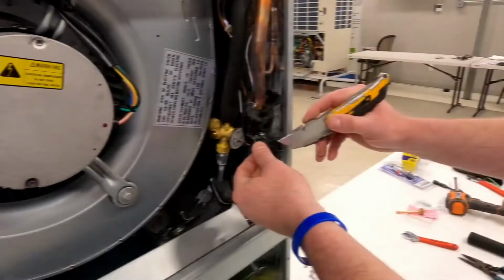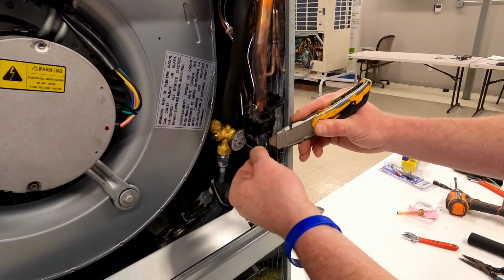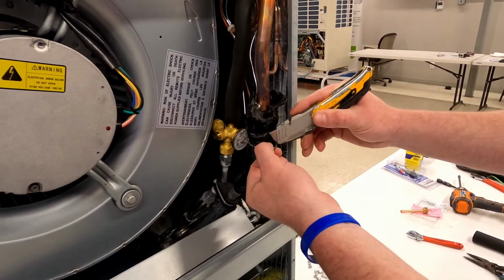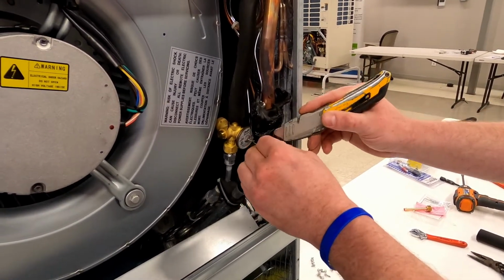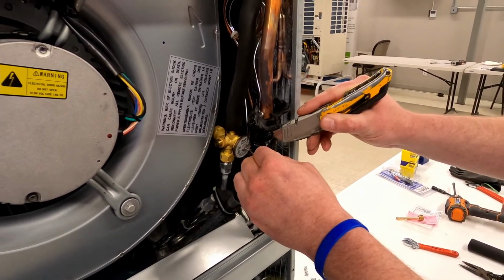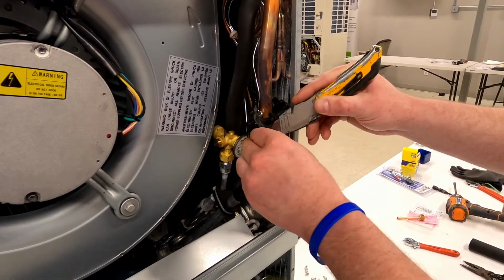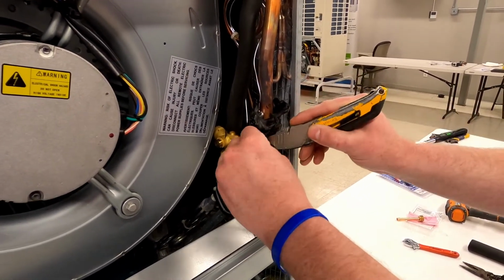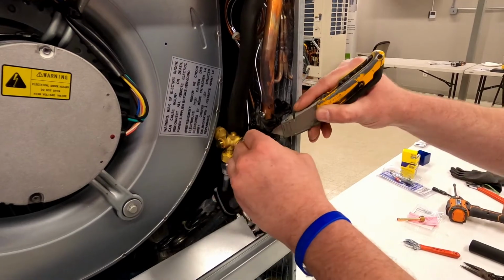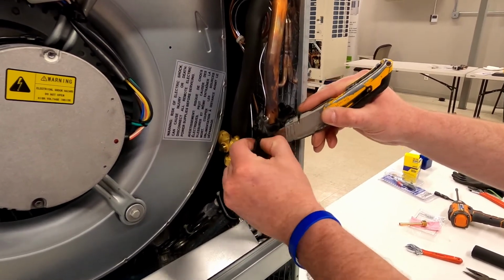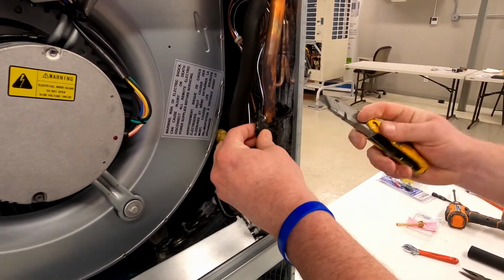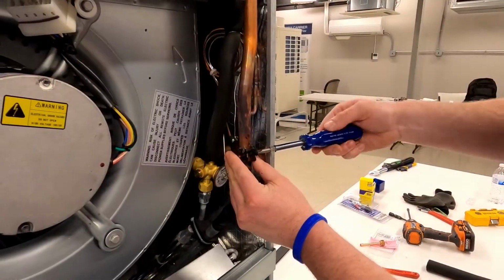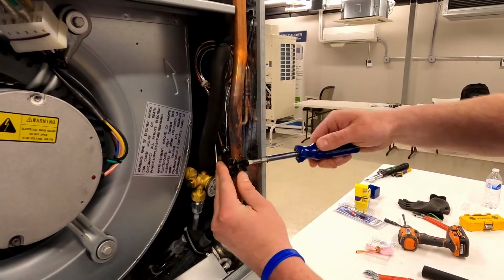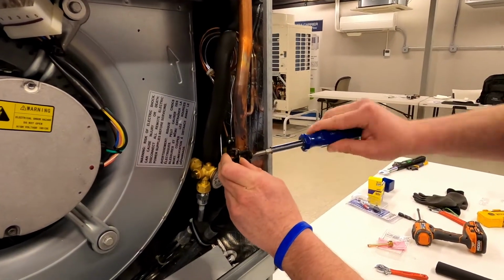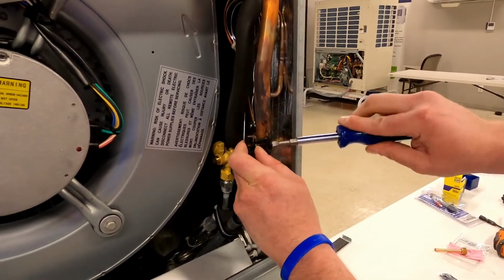All right, so when you're removing this insulation gum, you want to try and cut as carefully as possible and slowly peel it back. You don't want to chance gouging the suction line or cutting into the TXV sensing bulb. Alright, so now after we got the insulation off of it, we're going to remove our TXV sensing bulb from the suction line.